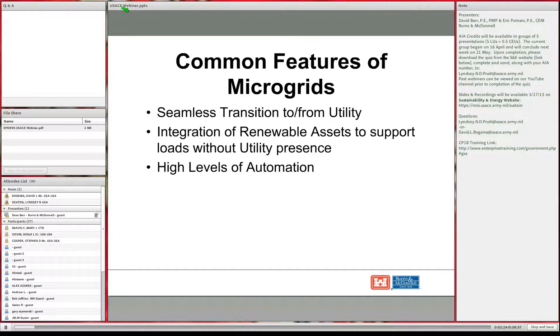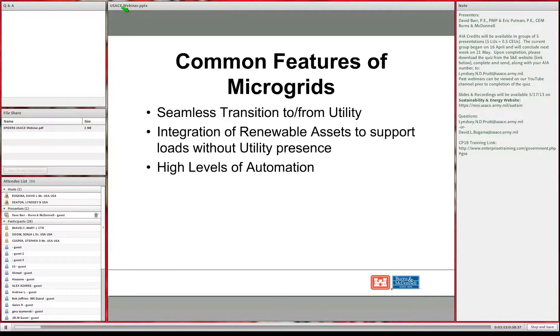A very important feature of a microgrid for the DOD is the ability to integrate renewable assets and support loads without a utility presence. Most renewable assets—whether a PV array or a wind turbine—rely on a utility signal for a stable grid reference to put out power. So if the utility is lost, the 2 megawatt PV array at Fort Carson, even on a sunny day, cannot provide power to the installation. A microgrid changes that, and also requires a higher level of automation than what exists in typical military base distribution systems today.